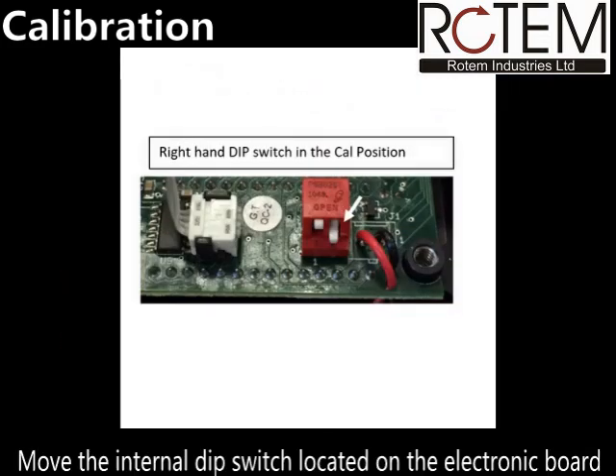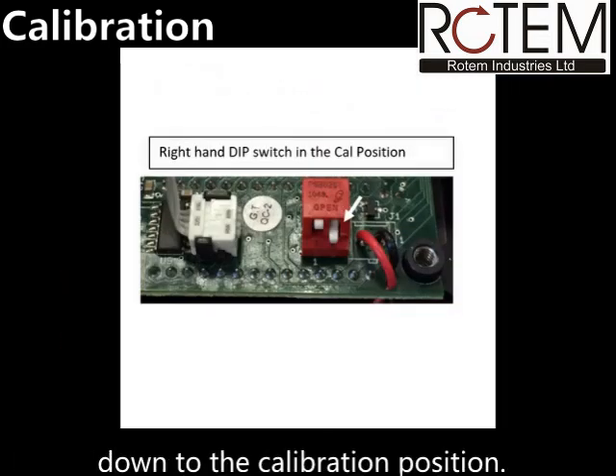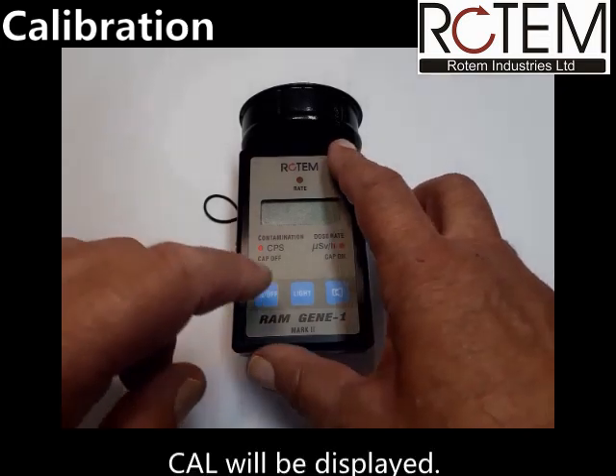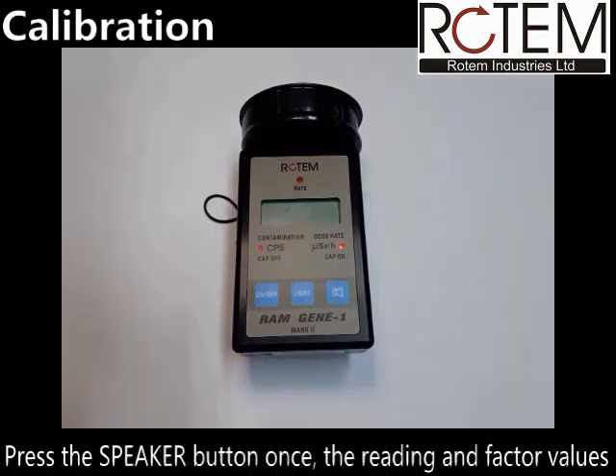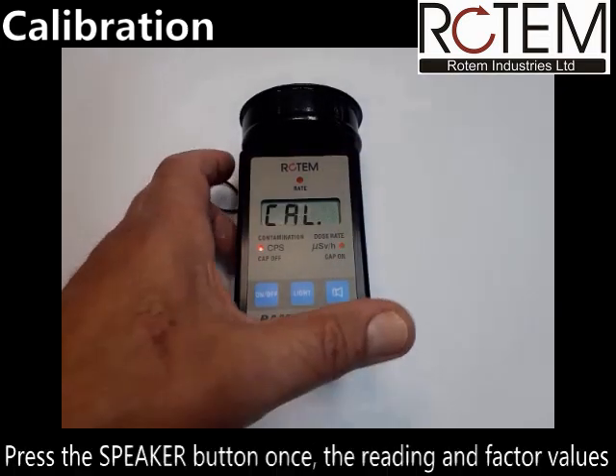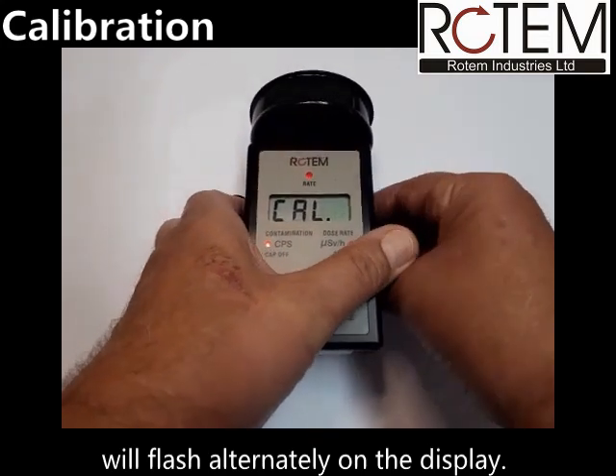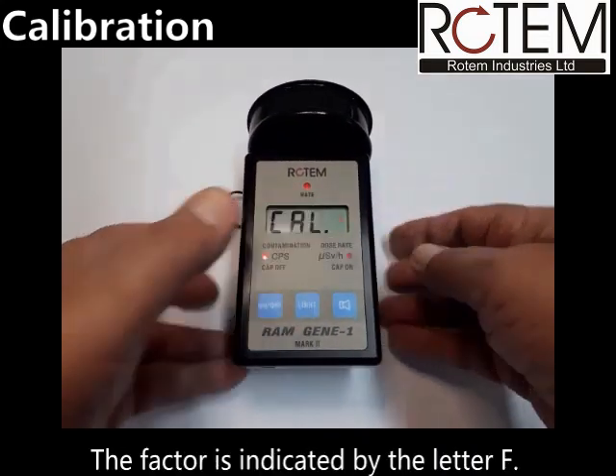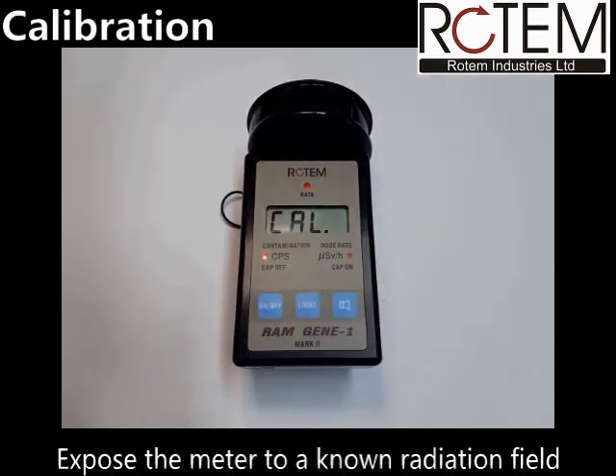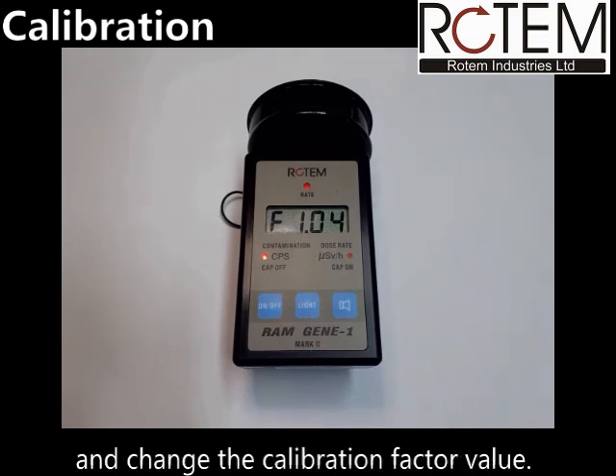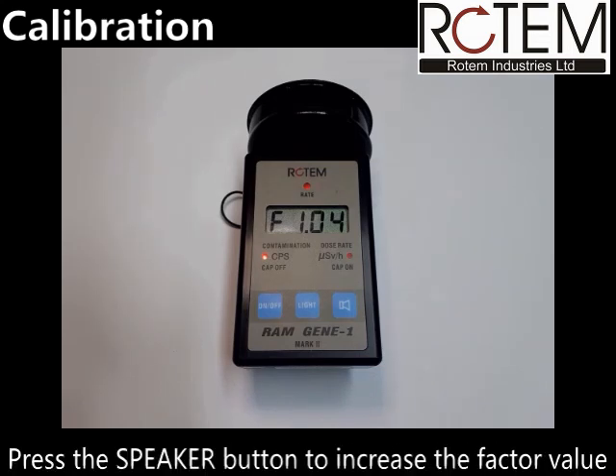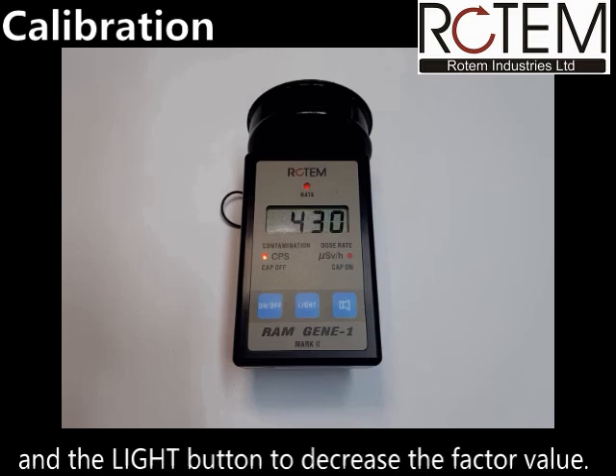Move the internal dip switch located on the electronic board down to the calibration position. Cal will be displayed. Press the speaker button once, the reading and factor values will flash alternately on the display. The factor is indicated by the letter F. Expose the meter to a known radiation field and change the calibration factor value. Press the speaker button to increase the factor value and the light button to decrease the factor value.